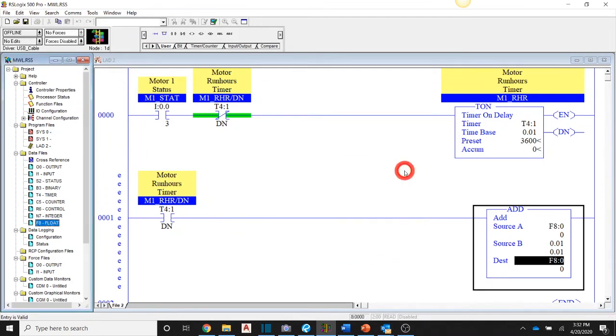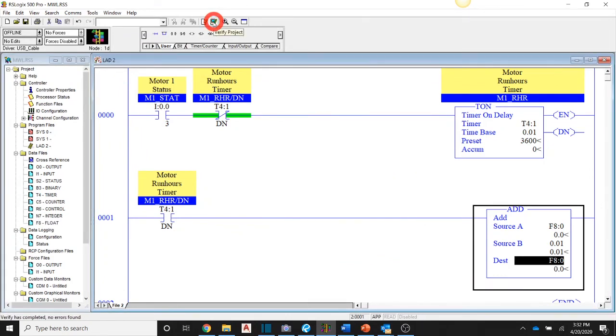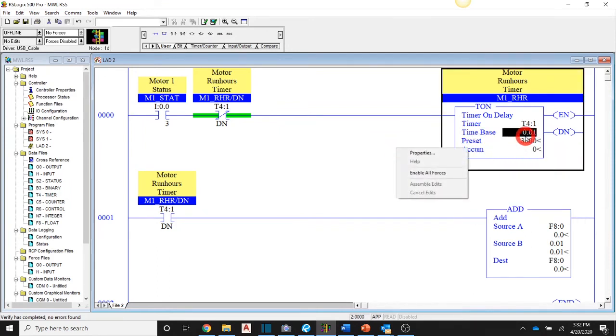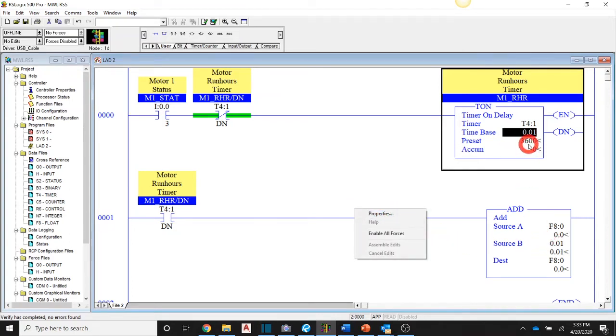And then I'm going to do another check, and that all is well. Okay, so let's review. We changed the time base to, instead of 1 second increments, to hundredths of second increments, and in doing so, we had to change this to the time base as well. So now every 36 seconds is 1/100th of an hour. We are going to add 1/100th to our hour.